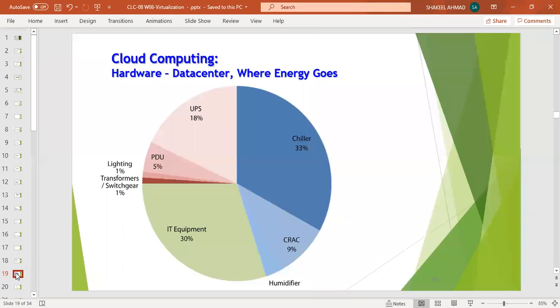This is the distribution of energy in a data center: UPS consumes 18% of the energy, chillers consume 33%, computer room air conditioning consumes 9%, IT equipment consumes 30%, lighting 1%, transformers and switchgear require 1%, and PDU consumes 5% of the energy.